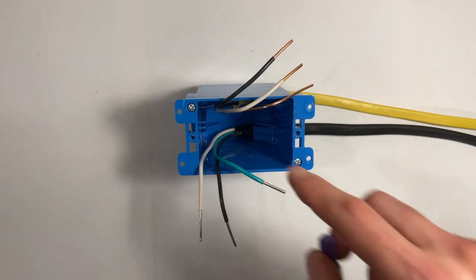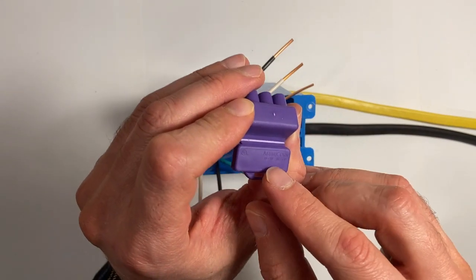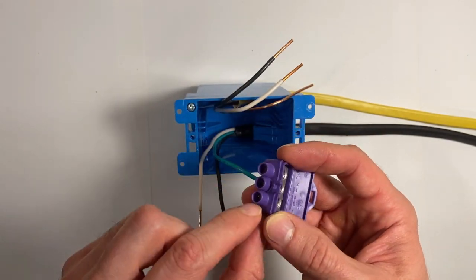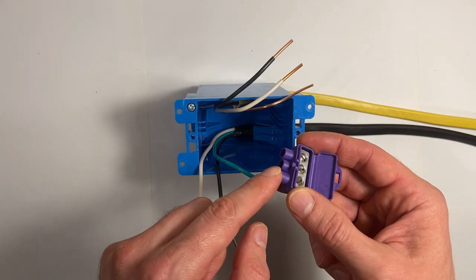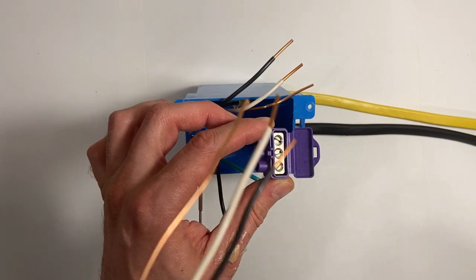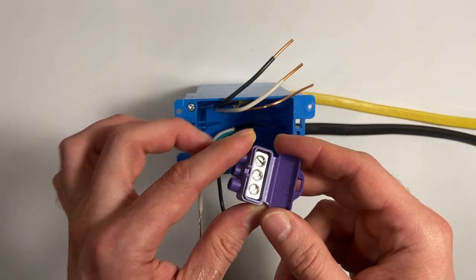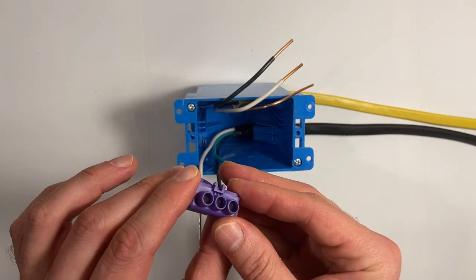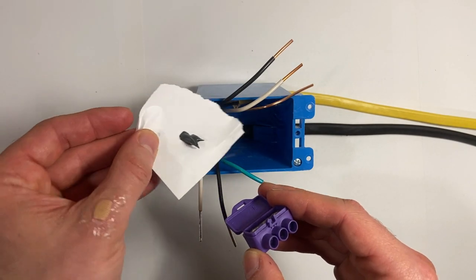Here's another product, this one is called Alumiconn. So Alumiconn, strictly one wire per hole. Again, you use one to connect to the existing aluminum solid wiring, and you can use two more, let's say one for the pigtail to an outlet and the other to continue the circuit out of this receptacle box. And as you can see, they too come stuffed with some sort of anti-corrosive paste.